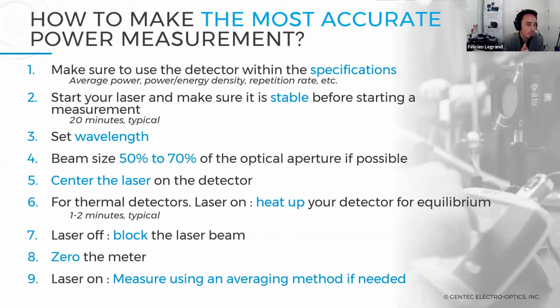Then block your laser beam. For a high power laser, that could be tricky. You cannot block it with a small card like you can for low power lasers. I've seen applications where you could use beam dumps placed in the optical path, turning off the laser beam. If you want the laser to be still functioning, you can use a beam dump to dump the energy, and then with the meter that's used for calibrated measurement, you can do the zero, then remove the beam dump and have 100% of the laser power going to the power detector.